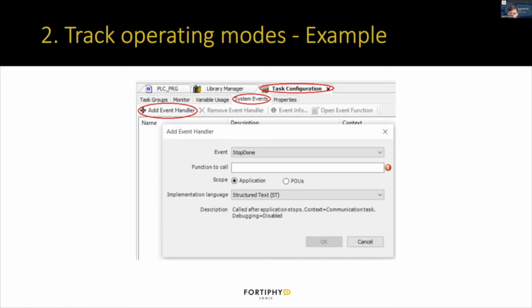Again, that key point: depending on how it's configured, depending on the PLC, the IO values may not update when the program is in stop mode. So it may look like it's still in run mode if you're just monitoring that value. So it's also really helpful to add an event handler to run some code to raise some alarm when the PLC does change to stop mode. For CODESYS, you can look at the task configuration page under system events and add an event handler for the stop done event, such as saying that when the PLC program stops, run this function or application or POU to do whatever you want to raise that alarm when it stops.